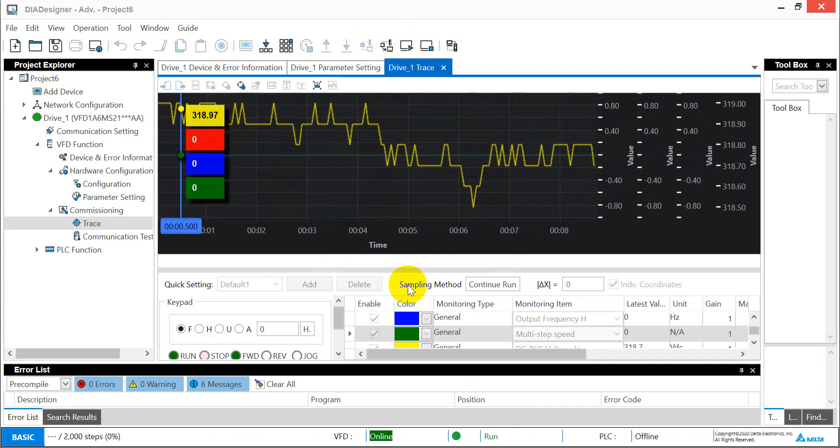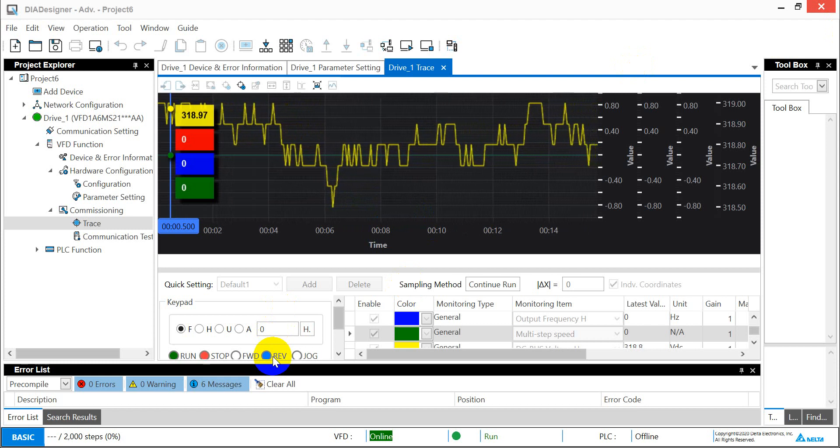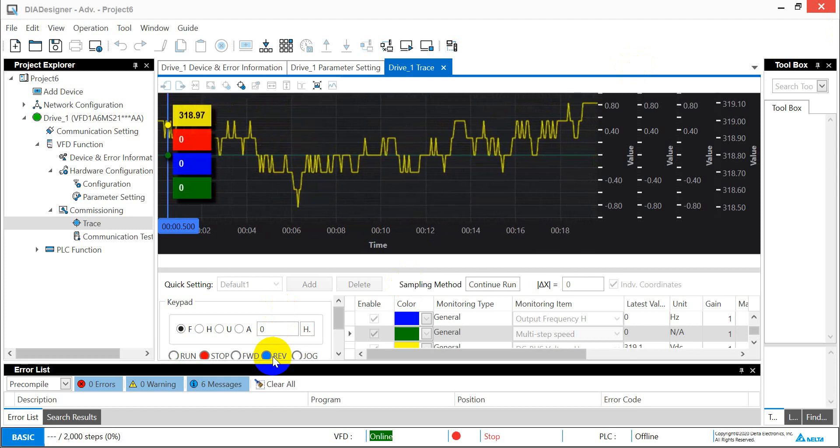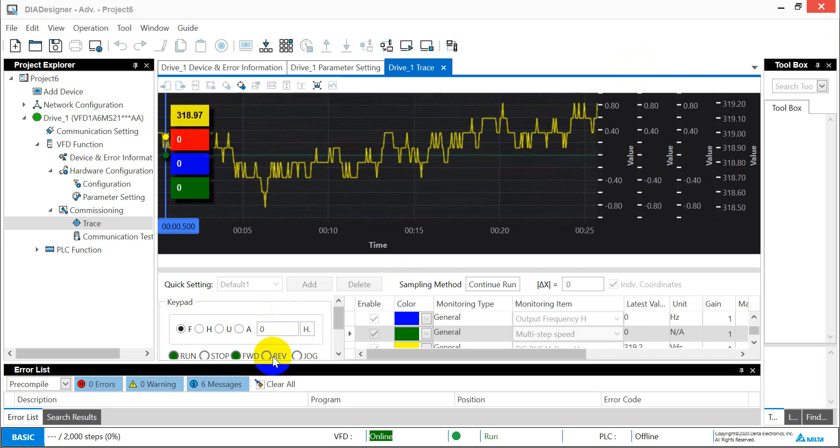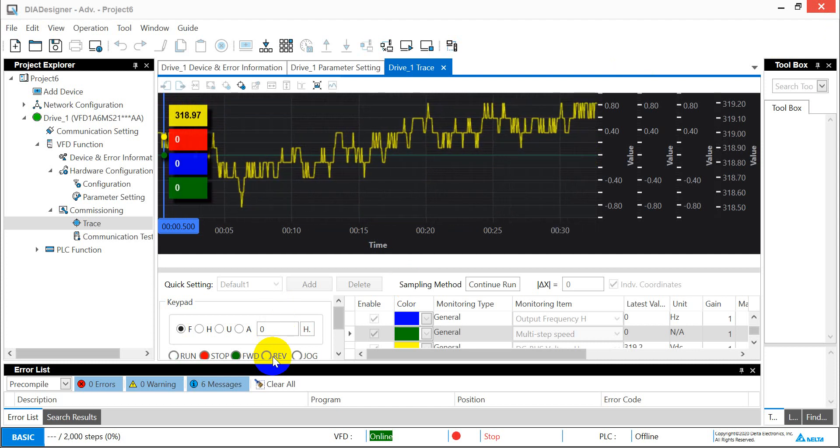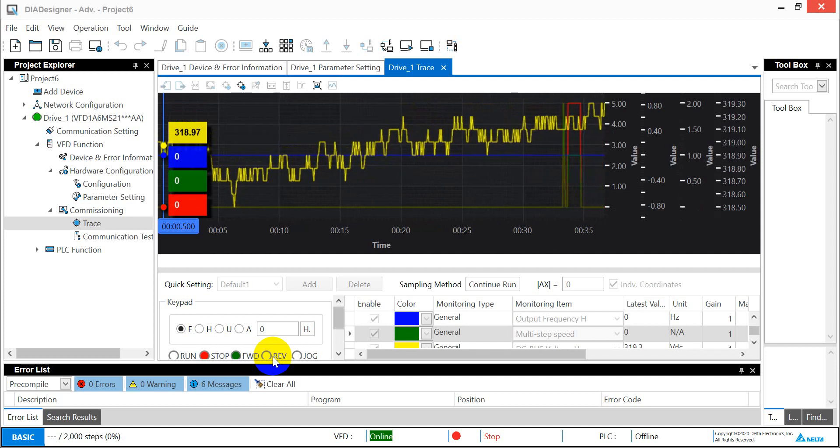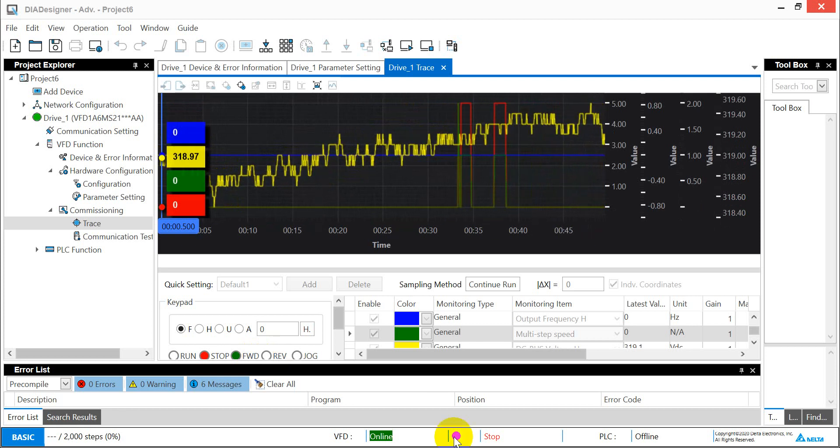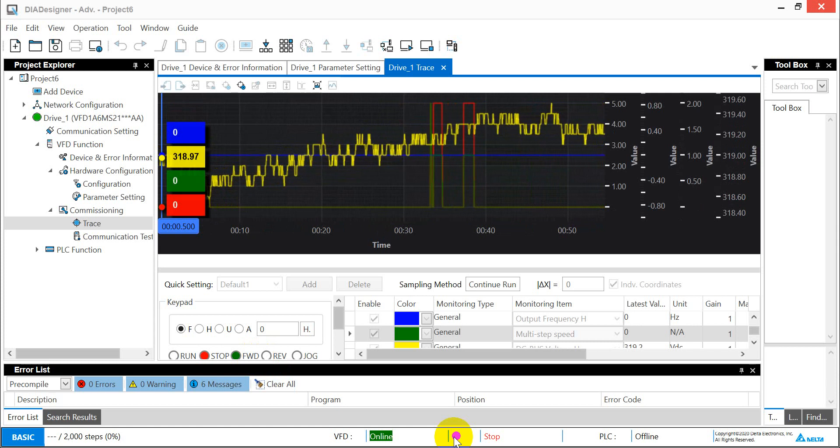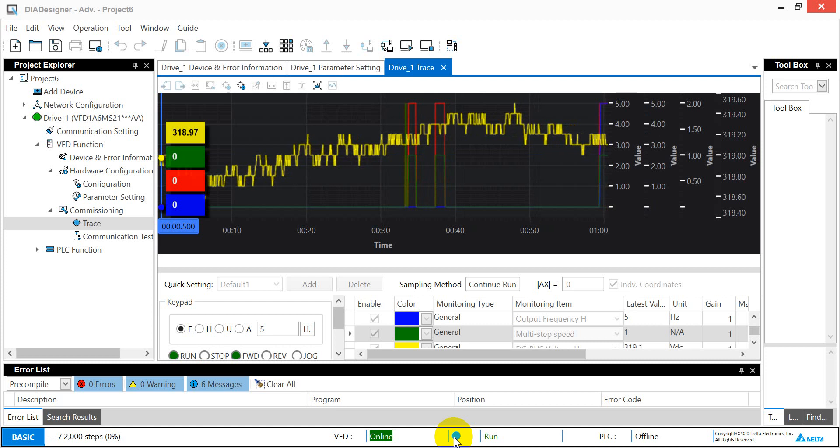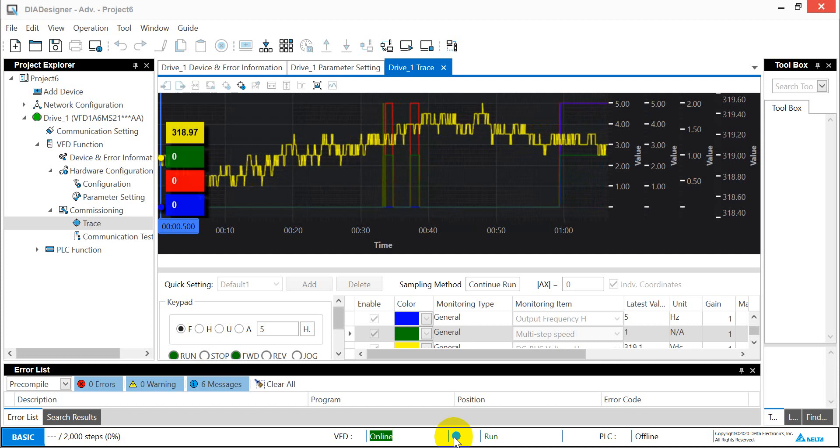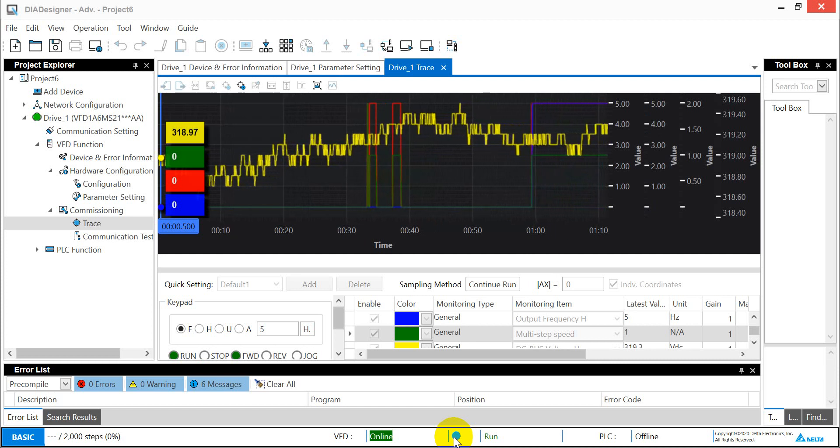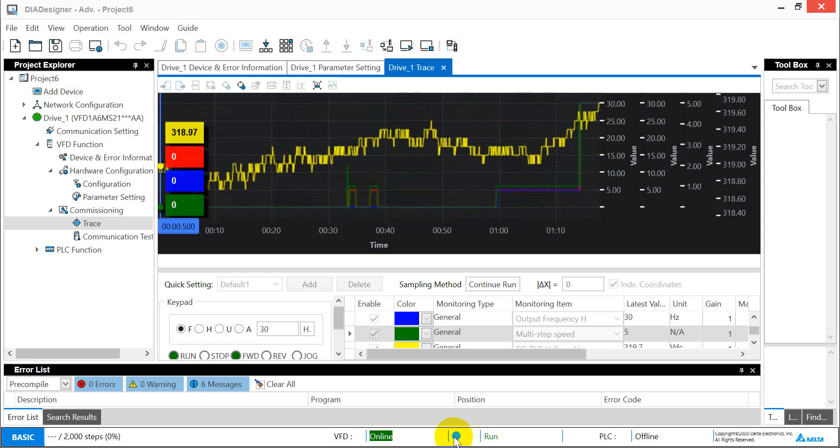We will connect forward first. If we change this one to MI2, you will see the indicator here will change to reverse. First we will connect to MI1, which means running forward. Next we will connect to MI3. Once we connect to MI3, we will see the frequency will be 5 Hertz. Then we connect to MI5. This one will keep forward but the frequency changes to 30 Hertz.